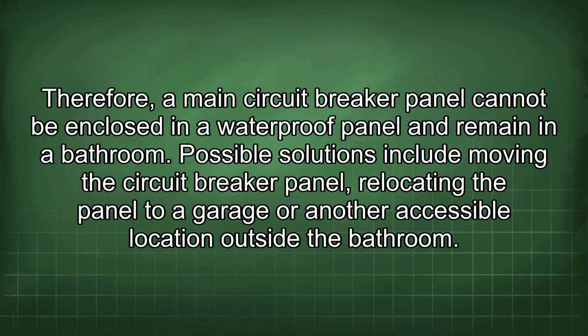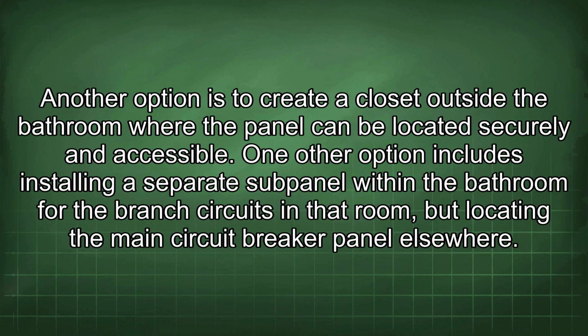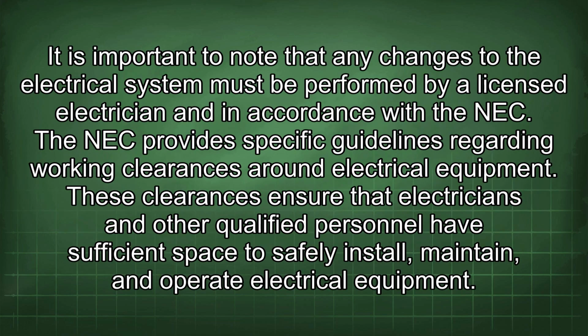Possible solutions include relocating the circuit breaker panel to a garage or another accessible location outside the bathroom. Another option is to create a closet outside the bathroom where the panel can be located securely and accessibly. One other option includes installing a separate subpanel within the bathroom for the branch circuits in that room, but locating the main circuit breaker panel elsewhere. It is important to note that any changes to the electrical system must be performed by a licensed electrician and in accordance with the NEC.